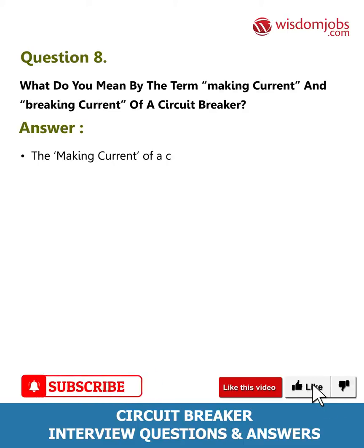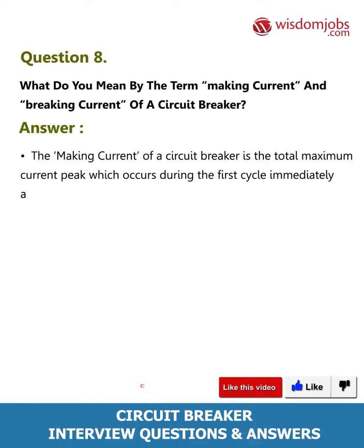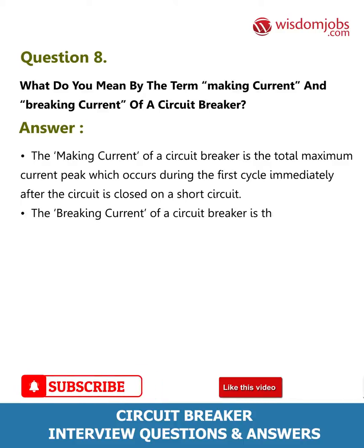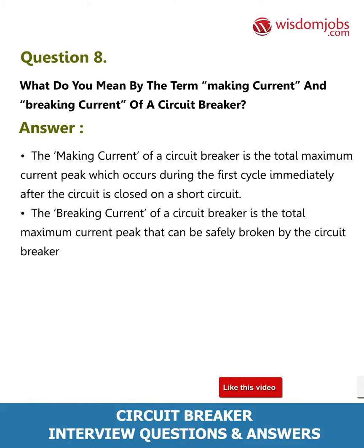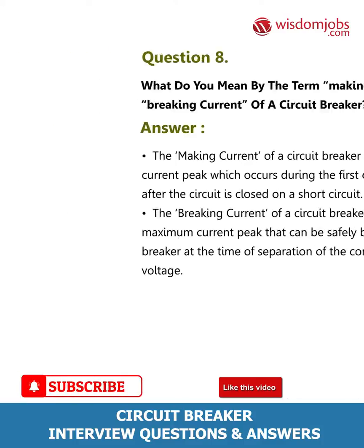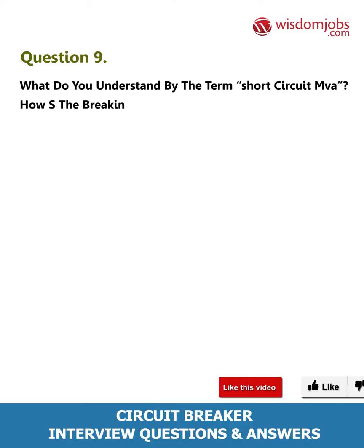Answer: The making current of a circuit breaker is the total maximum current peak which occurs during the first cycle immediately after the circuit is closed on a short circuit. The breaking current of a circuit breaker is the total maximum current peak that can be safely broken by the circuit breaker at the time of separation of the contacts at its rated voltage.